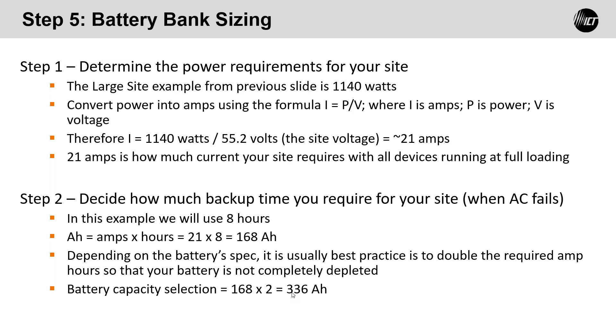So now we need to determine the battery spec, and it's usually best practice, as I mentioned earlier, to double the required amp hours so that the battery is not completely depleted. So if we multiply 168 times 2, we get 336 amp hours, which means we're going to need a lead acid battery that's about 336 amp hours. And obviously we probably have to round that up to whatever's available.